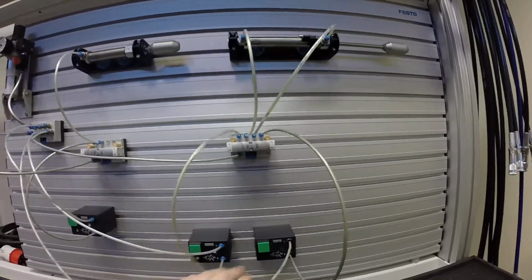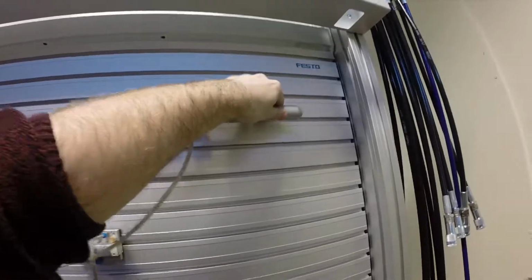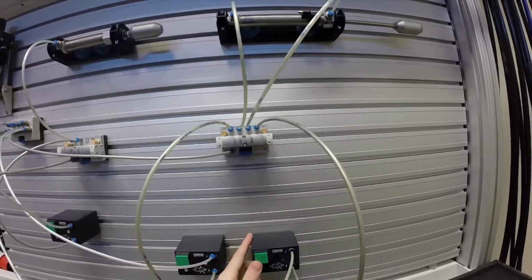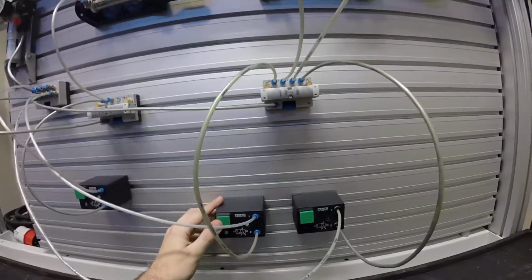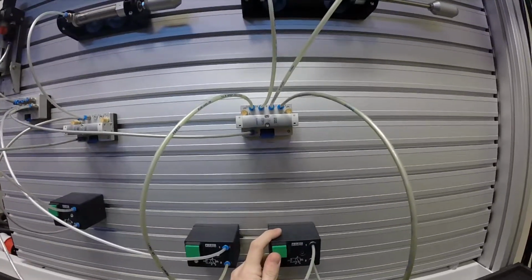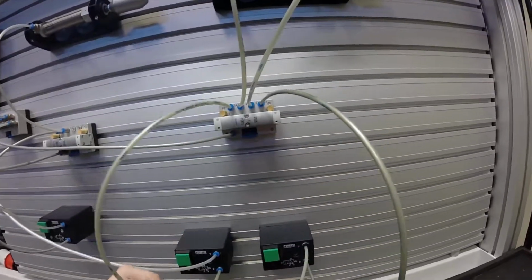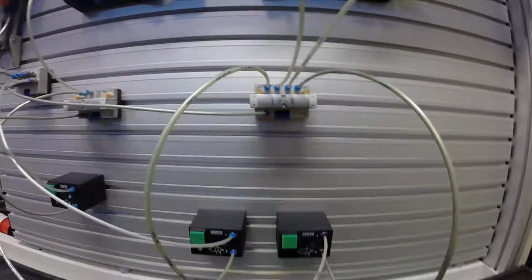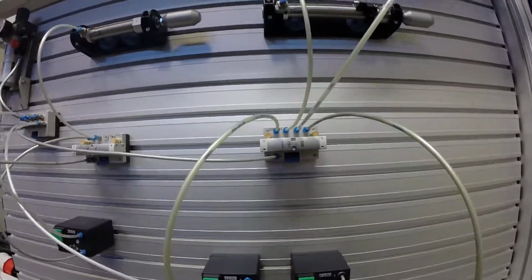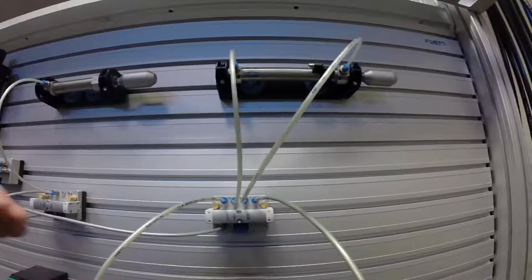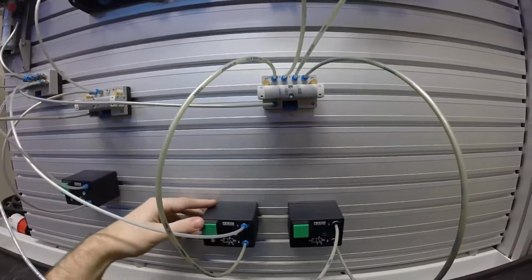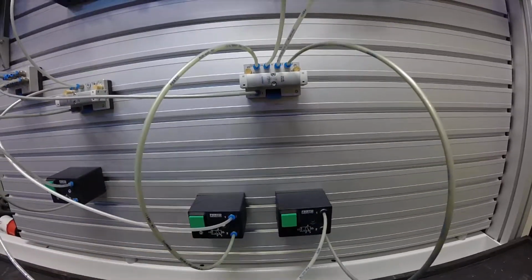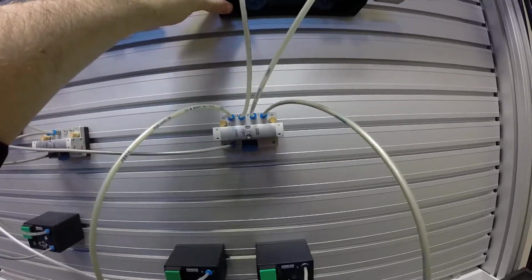When I push 1, it extends, and even if we check, that's fixed in position. I can't pull that, it's locked in position as the air is going through, and then I can retract it over on this side. So we're piloting both sides, taking a pulse in from both sides. Again, each one of these valves has its own air supply, so you could set up differential air supplies there. But basically we're just indirectly controlling this cylinder. Before, we were directly controlling, because this was piped directly into the cylinder, but now we're indirectly controlling it because we're going from here up to this pilot valve and then up to here.